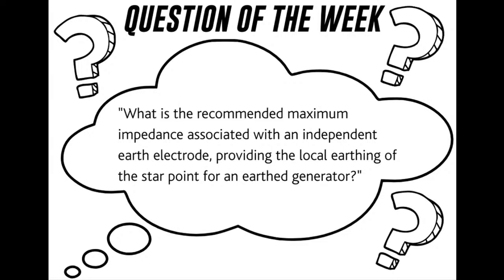Okay, all right. Well, without any further ado, we'll get straight into it. We'll just post out the question of the week that was put up on the Facebook and YouTube channels earlier today. So the question of the week was associated with generators. And it is, what is the recommended maximum impedance associated with an independent earth electrode providing the local earthing of the star point for an earthed generator? So a bit long-winded, but basically what's the recommended maximum impedance associated with an independent earth electrode that's providing the local earthing of the star point for an earthed generator?